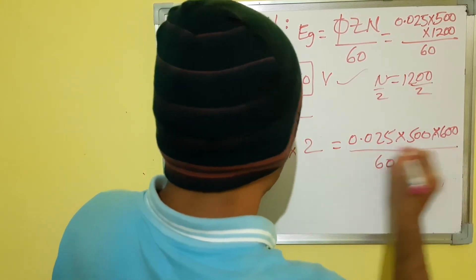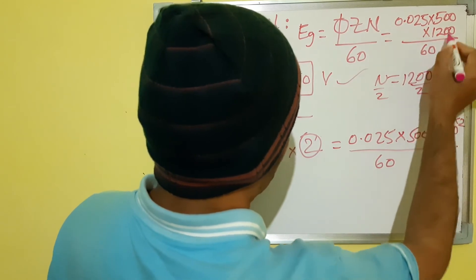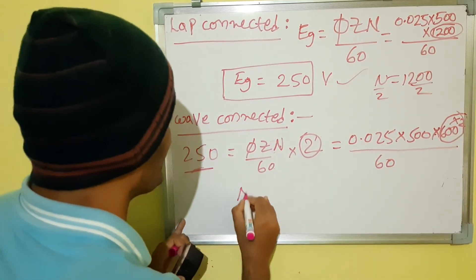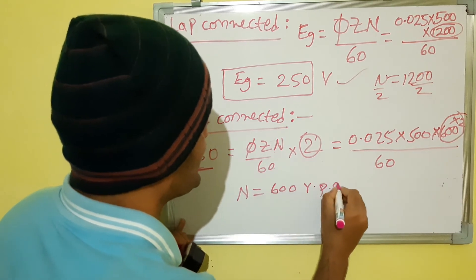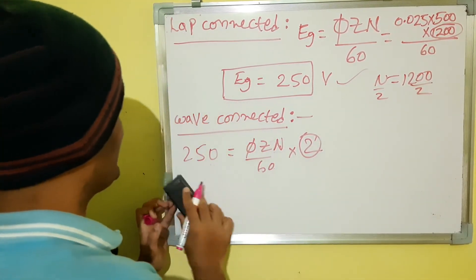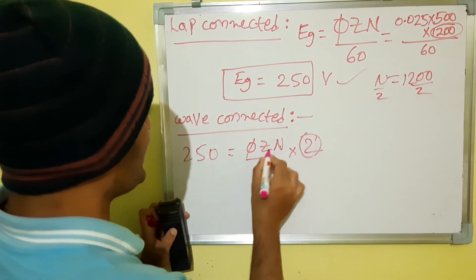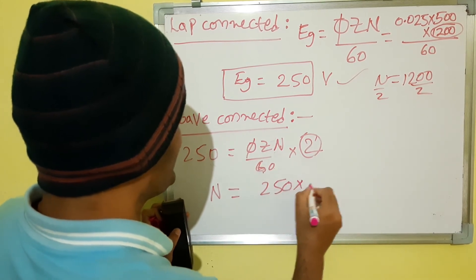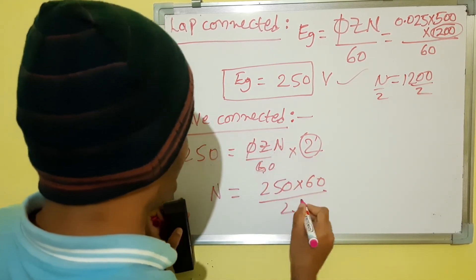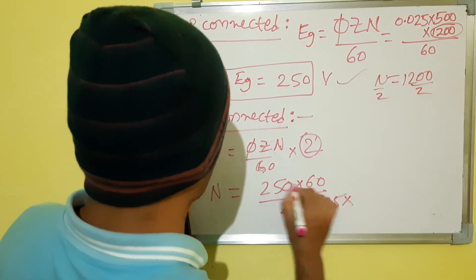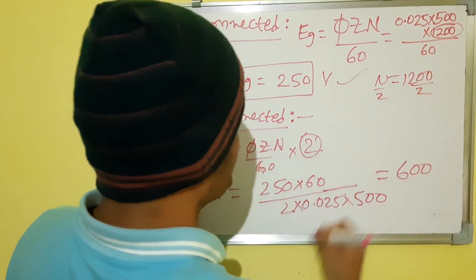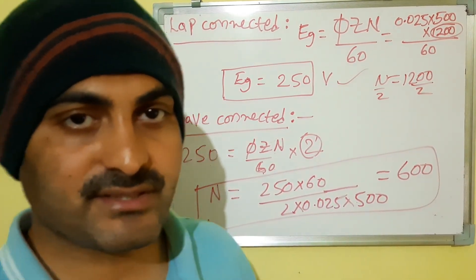So the factor becomes 2, and into 60, dividing by the factor 2, 1200 divided by 2 gives 600 RPM. For the wave connected machine, N equals 250 into 60 divided by 2 into 0.025 into 500, which gives N equals 600 RPM. Thank you engineers, thank you so much.